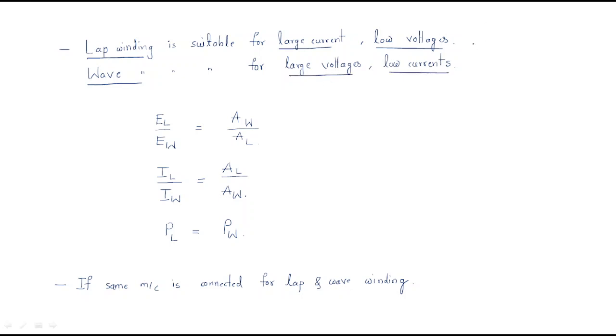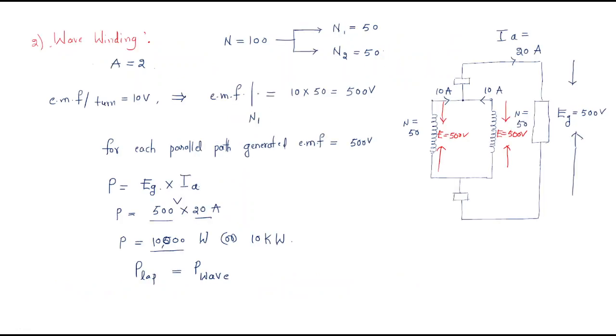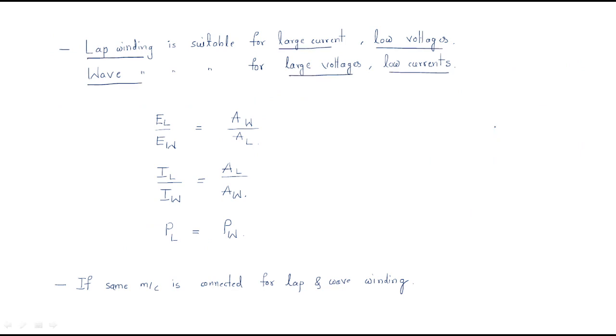Wave winding is suitable for large voltages and low currents. For the same power, the voltage is 500 volts and the current is 20 amps. So wherever high current is required, prefer lap winding; wherever high voltage is required, go for wave winding. The choice depends on the application.